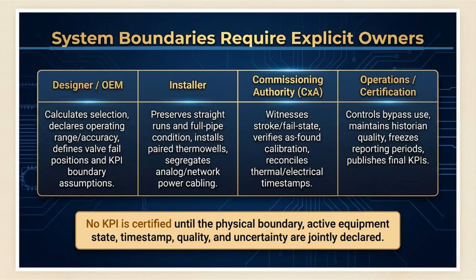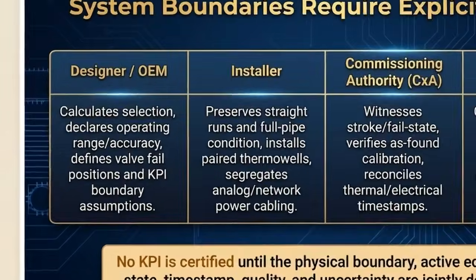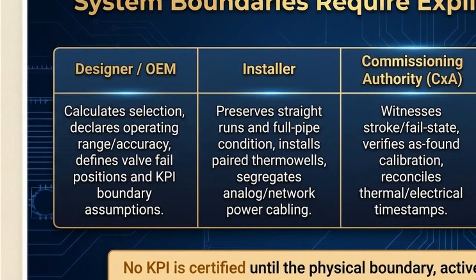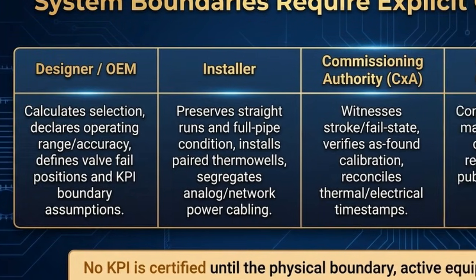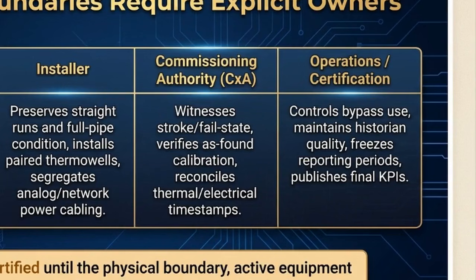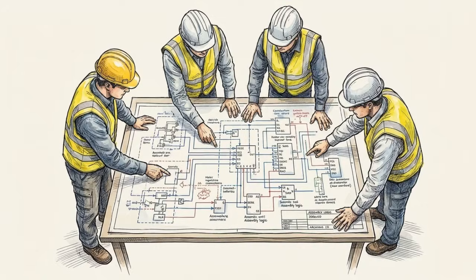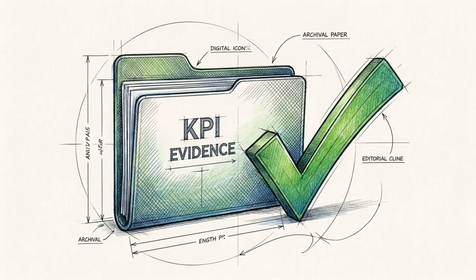This table defines the explicit owners of those system boundaries. The designer sets the operating range. The installer preserves straight-run pipe conditions. The commissioning authority verifies calibration, and the operations team publishes the final metrics. A performance metric is not certified until all of these boundary owners jointly declare and verify the physical and mathematical rules governing it. The metric only exists when the evidence supports it.